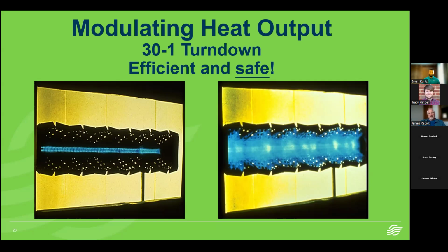And it's also safe. That burner you're looking at there burns approximately 100 times cleaner than the gas range or oven in everybody's home. Nobody gives a thought to that, when you don't want to use them for heat, et cetera, because they don't have outside air coming in to dilute the contaminants. We are not only burning 100 times cleaner than those gas stoves and ovens in everybody's house, but we're bringing in outside air to dilute it. OSHA and ANSI standards allow us to add up to 5 parts per million of carbon monoxide to the air coming in. In practice, it's typically around 2 or 3, no matter what the burner modulation range is. So this is very safe and very, very efficient.